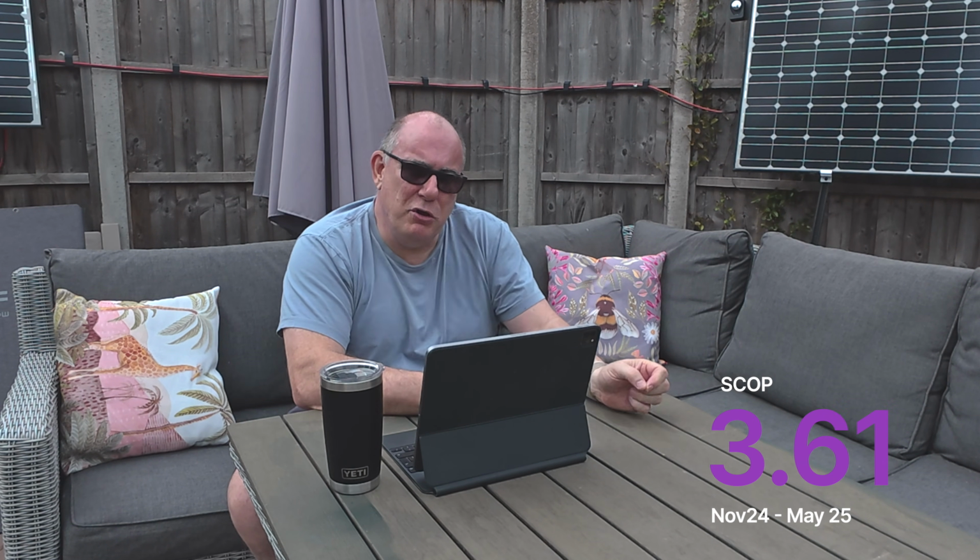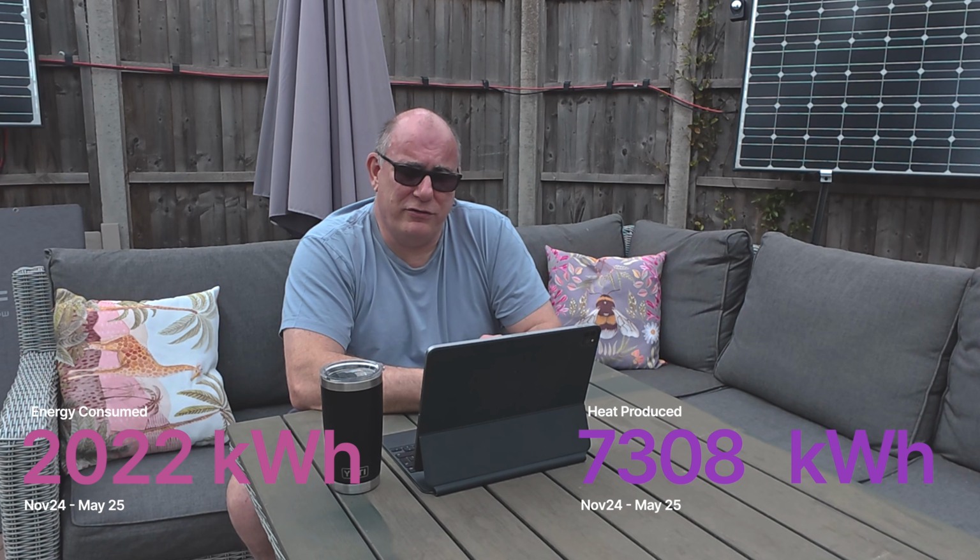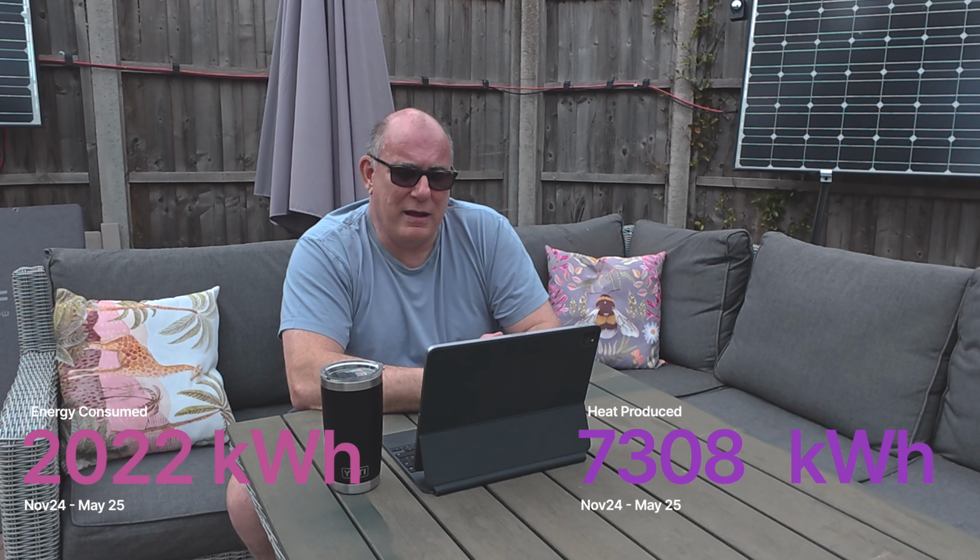That means for every unit of energy that we put into our heat pump, we get 3.61 units of energy out. With a gas boiler, for every unit of energy you put in, you'll be lucky if you get 0.9 units of heat out of it. So we used 2,022 kilowatt hours of electricity, and we produced 7,308 kilowatt hours of heat.